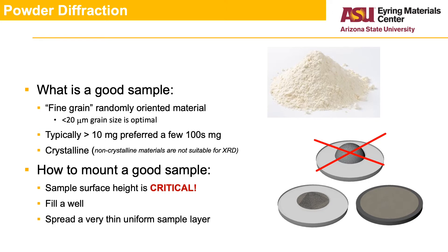The sample should have a smooth flat surface, and the sample surface must be at the correct height. Whether filling a well in the sample holder or creating a very thin layer of powder on a flat holder, the sample must not look like a dome or pile of sample — it should be flat.